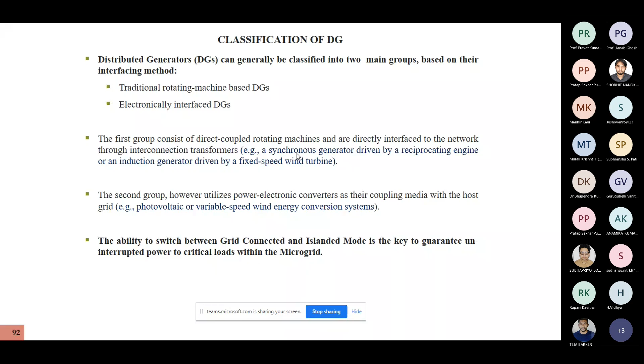It has not still become a mature technology as far as utility professionals are concerned. But at the same time, the protection aspect with DG penetrated brings another aspect: the contribution to short circuit current and the inertia I talked about. Then you have to consider other things, such as blinding of protection, false sympathetic tripping, loss of fuse-recloser coordination, unsynchronous reclosing, and the provision of automatic reclosing.